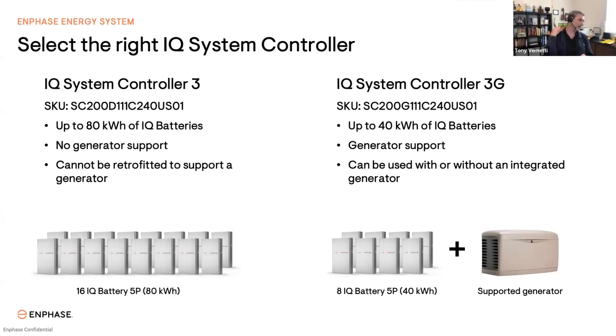And while we're on that note, let me just review the value of a generator with Enphase. With Enphase, a generator can actually be connected directly into the system controller, like I said, and it can operate simultaneously with solar and storage. In almost every other configuration out there that says that they're generator compatible, the way it works is the generator is on an automatic transfer switch, and if the battery system runs out of power, runs out of energy, that system can switch over to the generator. So basically the battery turns off, the generator turns on.